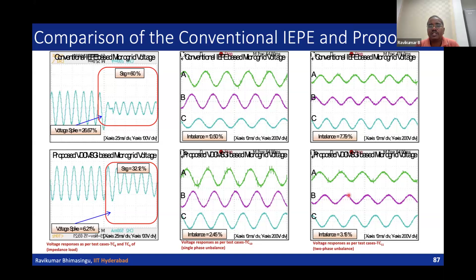So if you summarize all these results in a tabular form, the red ones are the violations. As per the standard, it should be limited to 800, but it has crossed 1120 in both the cases. In this case, it is 1350. Here the voltage imbalance is 3%, here it is 3.16, little variation, but in all other cases, the conventional IEPE is also violated for many performance indices.